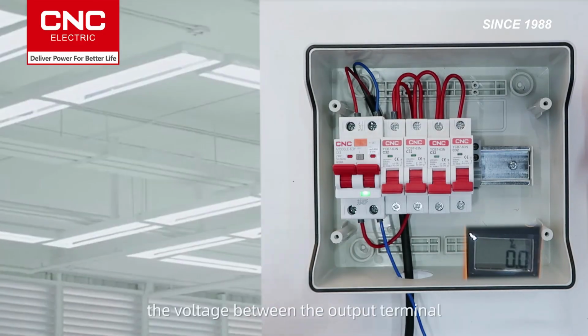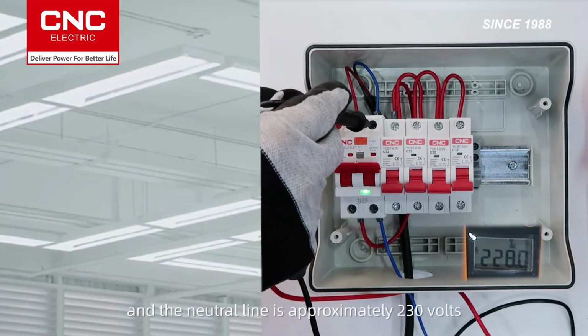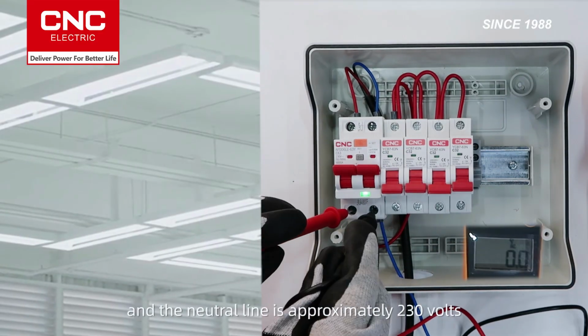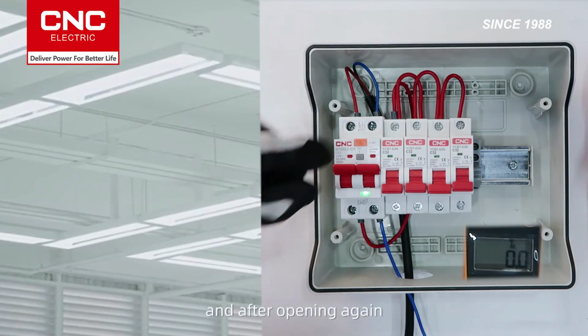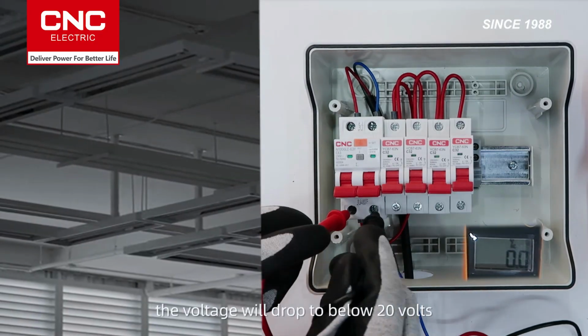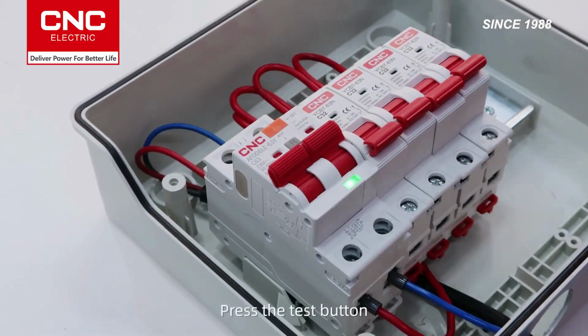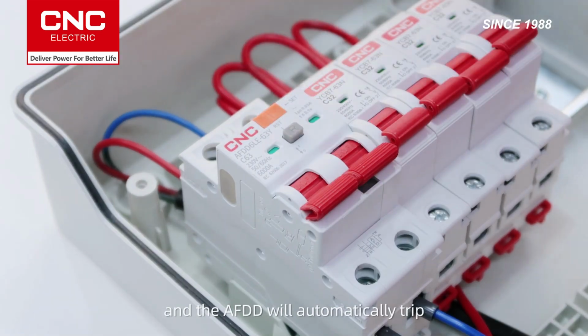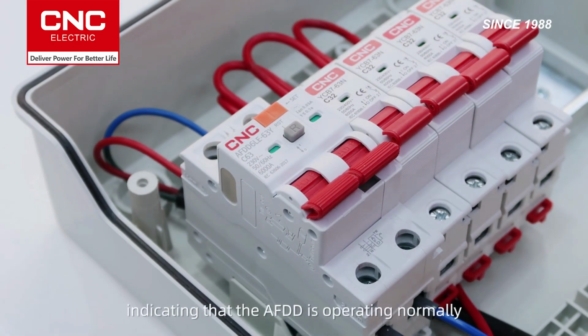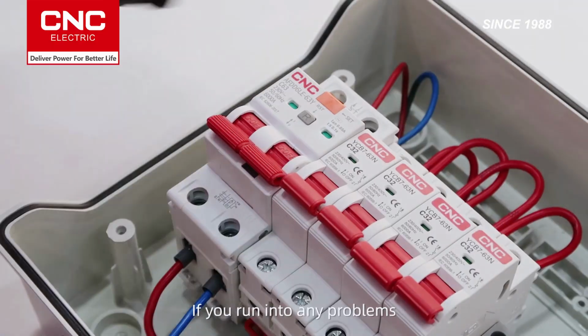After closing, the voltage between the output terminal and the neutral line is approximately 230 volts. And after opening again, the voltage will drop to below 20 volts. Press the test button, and the AFDD will automatically trip, indicating that the AFDD is operating normally. If you run into any problems, check the troubleshooting guide.